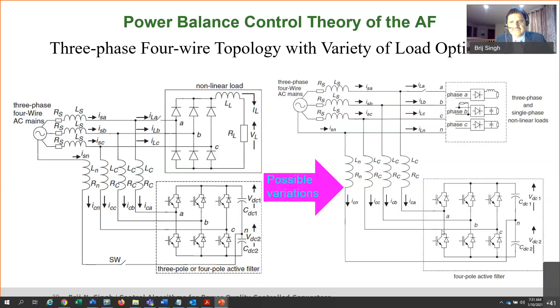If you have that, you can put a converter like this to compensate the harmonics, reactive power, and balancing, since the load may also not be balanced. This system can balance the load too. At this point, the supply system will see, from right here onward, a 3-phase balanced sinusoidal system - that's what you'll get if you do proper control and proper design.